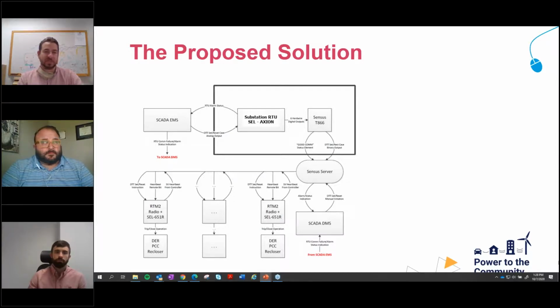So it ensures that nothing could go backwards and get into our EMS system. From there, Sensus goes up to their server, which has the automation control and control action routine logic running all the time, looking at the conditions from the T866 and making decisions that go out to the reclosers to trip the sites or bring them back online.